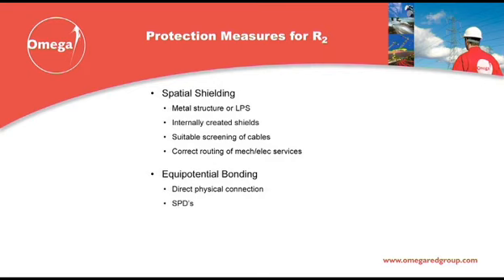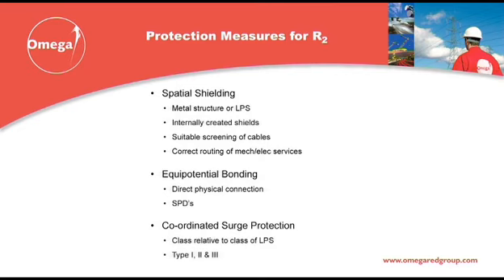Of course, it is important to ensure that equipotential bonding is provided between incoming services and the internal building services by means of Type 1 lightning current surge protection devices. This bonding surge protection device may not provide protection of electronic systems and is there to prevent dangerous potentials being developed and causing sparking in the event of a strike. It is important to ensure that these equipotential bonding surge protection devices are of the same level of protection as the structural lightning protection.